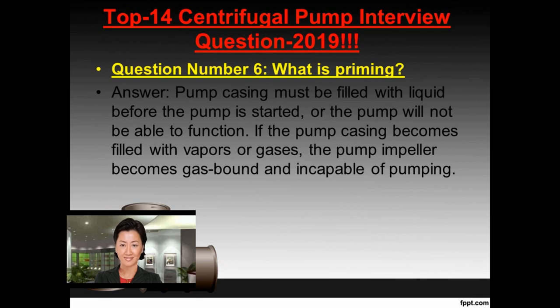Question number 6. What is priming? Answer. The pump casing must be filled with liquid before the pump is started, or the pump will not be able to function. If the pump casing becomes filled with vapors or gases, the pump impeller becomes gas-bound and incapable of pumping.